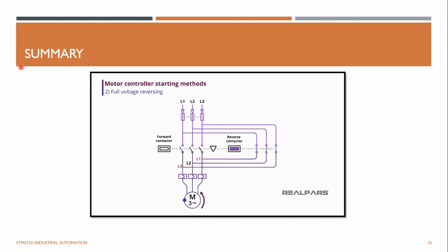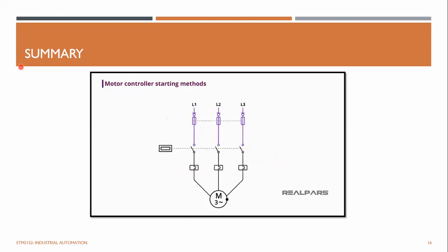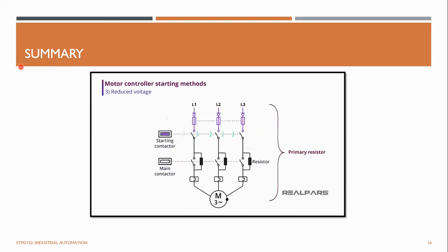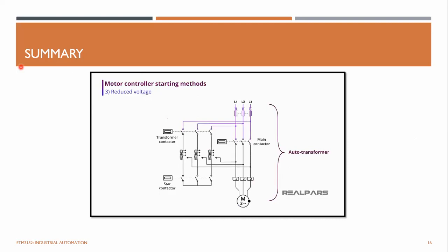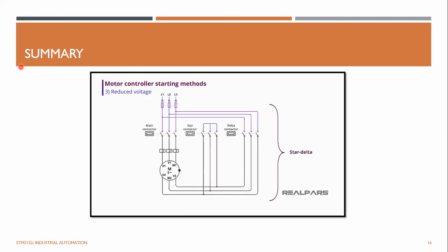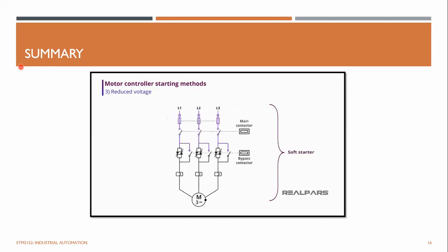very damaging. The third type of motor starting method is called reduced voltage starting. Large motors can have a very high starting current that may be harmful to the motor or the motor controller itself. To limit the amount of starting current to these motors, this type of motor controller applies a reduced voltage to the motor when it first starts. There are several ways to accomplish this, such as auto transformer, star delta, and soft starter. These will be described later.